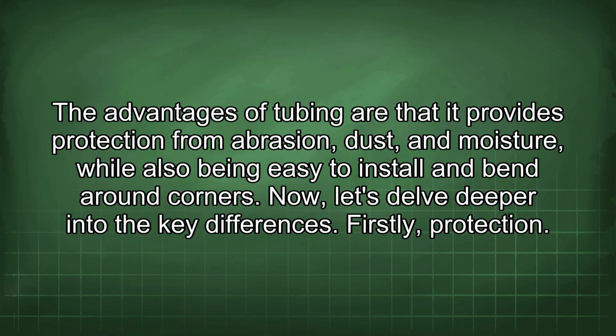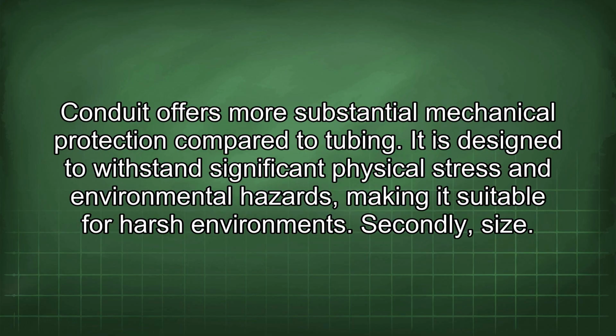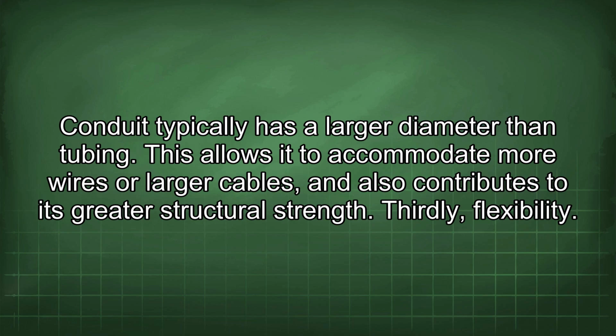Now let's delve deeper into the key differences. Firstly, protection. Conduit offers more substantial mechanical protection compared to tubing. It is designed to withstand significant physical stress and environmental hazards, making it suitable for harsh environments. Secondly, size. Conduit typically has a larger diameter than tubing. This allows it to accommodate more wires or larger cables, and also contributes to its greater structural strength.